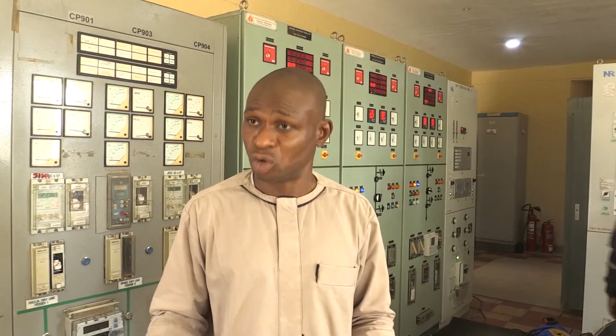So we now inform them. Though we have already informed them, it's just a reminder now, that we have been given approval through our area control, so that they can remind their stakeholders as well. Having informed them, we now go ahead and take out the 33 kV feeders on that equipment, the transformers. Then we take out the transformer and isolate it, so that the maintenance man will be able to work perfectly without any hazard.